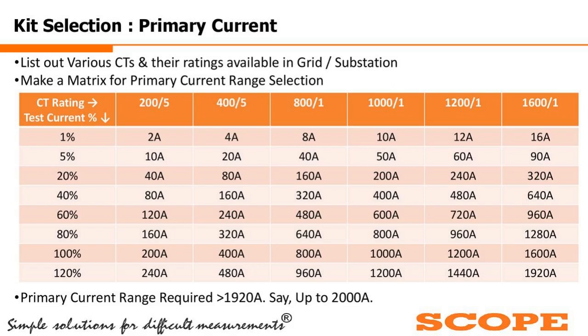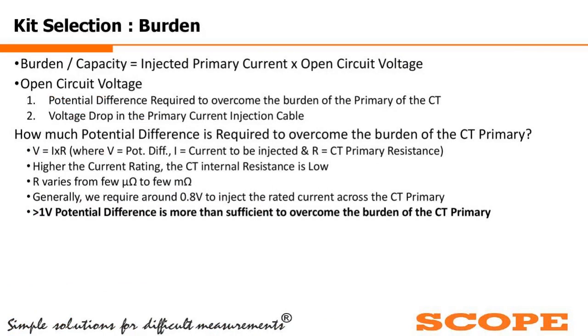In some cases — about 10% — CT ratings are 2000A or 2400A; for those cases a 3000A instrument can be selected. These are the combinations we can choose. For kit selection, two major doubts are: what is the burden or capacity, and what open circuit voltage is needed? The basic formula is: V = I × R, where V is the potential difference, I is the primary current injected, and R is the CT primary resistance. The open circuit voltage is simply the voltage drop needed to overcome the burden of the CT primary.